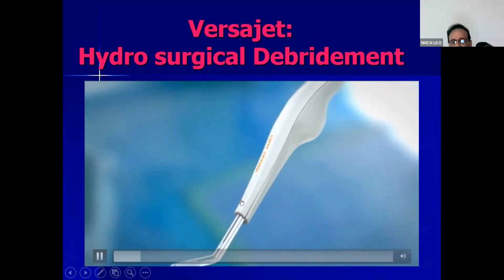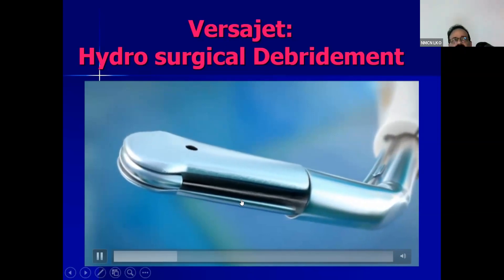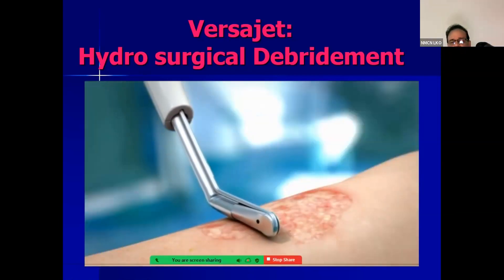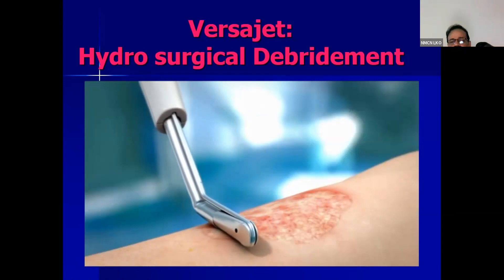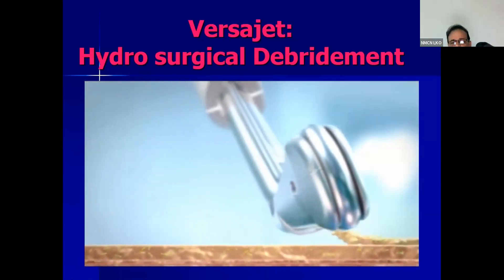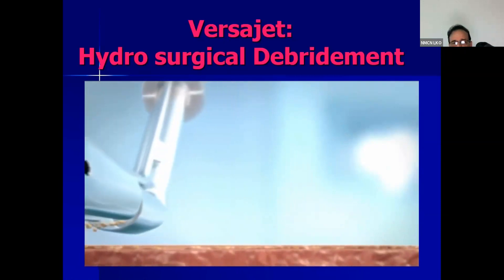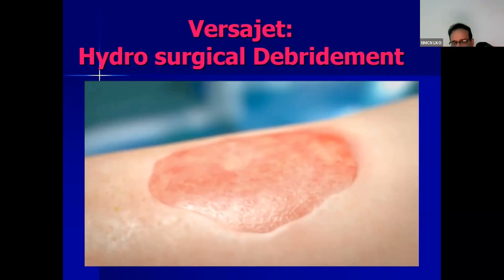Next is the Versajet, which uses a hydrosurgical debridement technique. Versajet is a handheld device in which a high velocity stream of sterile fluid jets across the operating window and into an evacuation tube. Versajet's Venturi effect creates a localized vacuum which holds and cuts tissue while aspirating debris from the site. At its lowest power levels it functions mainly as a vacuum and removes little or no tissue. As the power increases, Versajet removes a greater amount of necrotic tissue and bacteria. At the highest power levels, it removes non-viable tissue very rapidly and tackles all but the hardest eschars while preserving as much healthy dermis as possible.